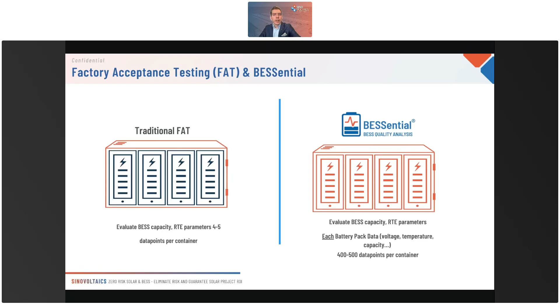That's the reason why we developed a software called BESSential. There we can dig inside of the container to see how each and every module and rack is performing against their specifications. If those don't comply, the modules can be replaced at the factory, which saves a lot of time and headaches at the site acceptance testing.